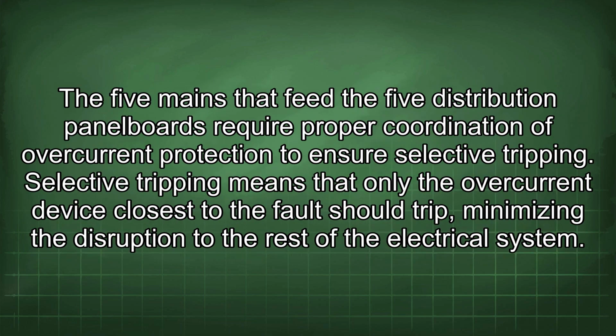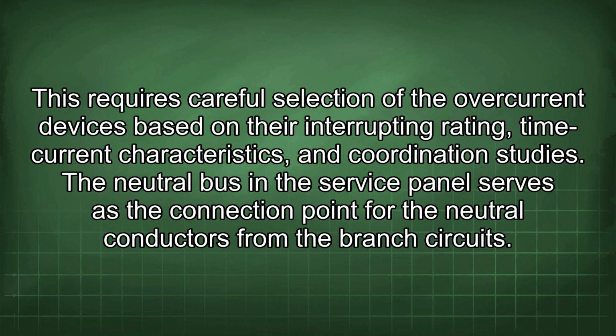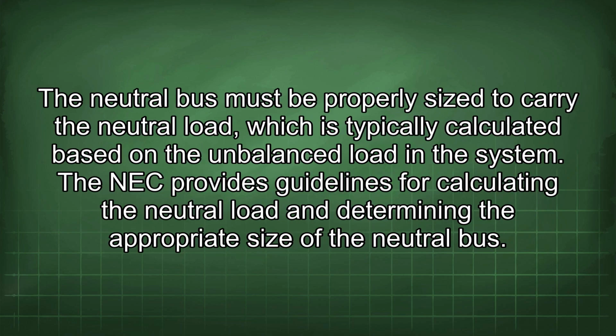The 5 mains that feed the 5 distribution panel boards require proper coordination of overcurrent protection to ensure selective tripping. Selective tripping means that only the overcurrent device closest to the fault should trip, minimizing the disruption to the rest of the electrical system. This requires careful selection of the overcurrent devices based on their interrupting rating, time current characteristics, and coordination studies. The neutral bus in the service panel serves as the connection point for the neutral conductors from the branch circuits. The neutral bus must be properly sized to carry the neutral load, which is typically calculated based on the imbalanced load in the system.